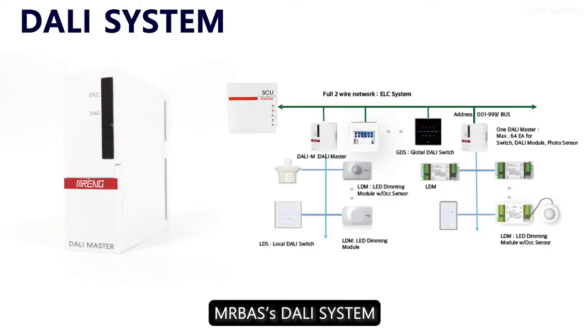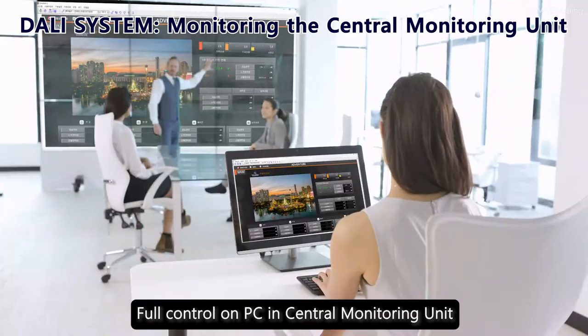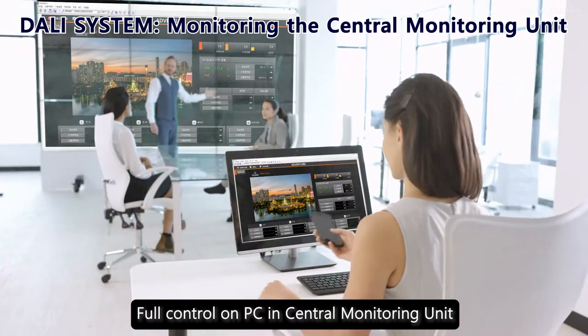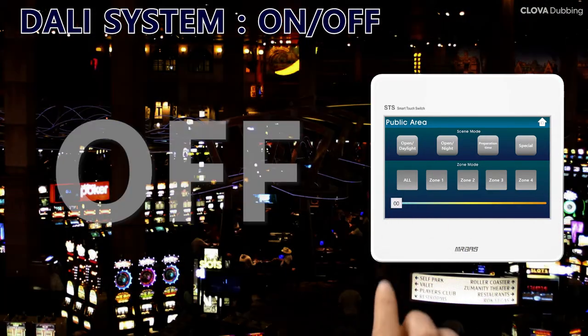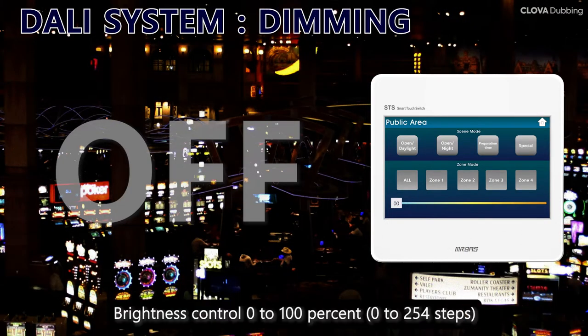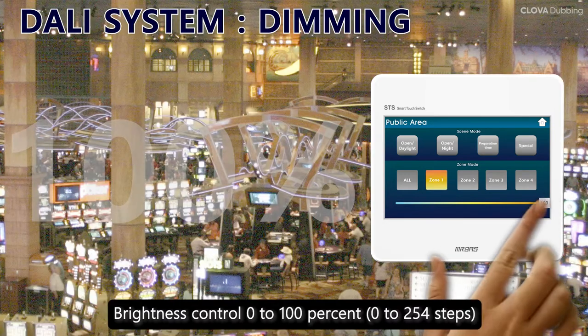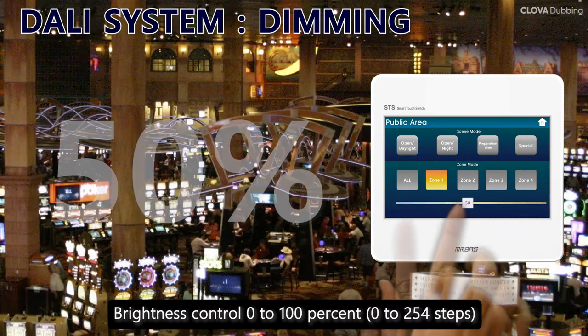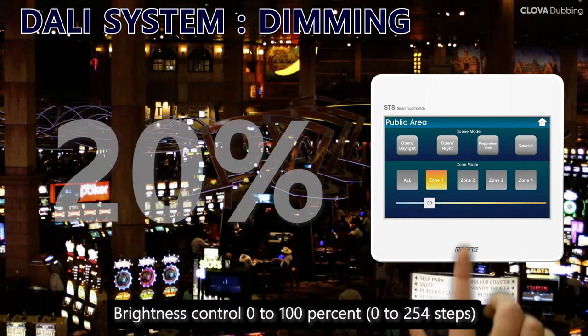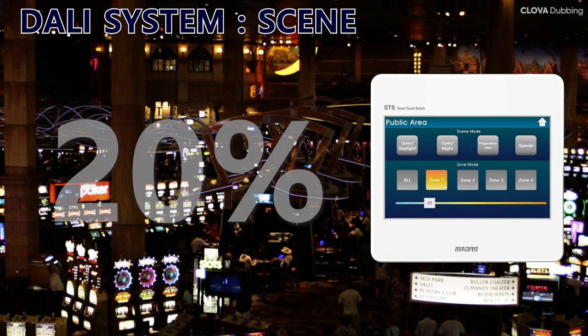The interior is composed of our DALI system and can be monitored and controlled at the PC of the central monitoring board. On and off and dimming controls allow 100%, 50%, and 20% settings for users to control the illumination they want using the on-site switch, to create a variety of illuminations in the casino area.